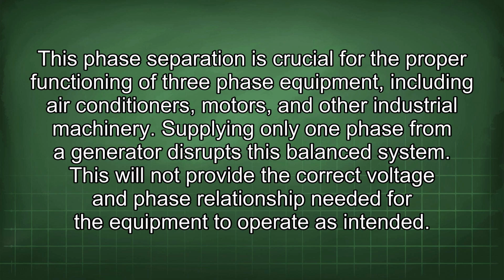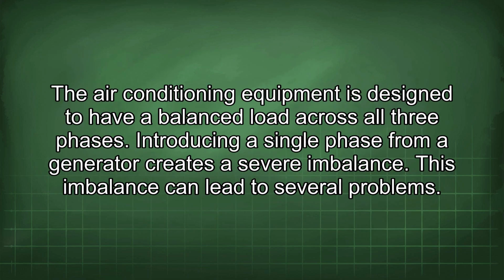Supplying only one phase from a generator disrupts this balanced system. This will not provide the correct voltage and phase relationship needed for the equipment to operate as intended. The air conditioning equipment is designed to have a balanced load across all three phases. Introducing a single phase from a generator creates a severe imbalance. This imbalance can lead to several problems.